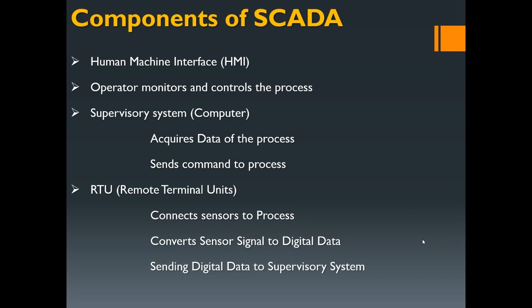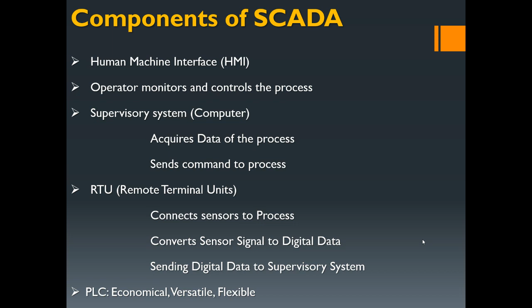Then we have PLCs, programmable logic controllers. They are connected to the sensors and actuators in the process, and they are networked to the supervisory system in factory automation. The PLCs typically have a high-speed connection to the SCADA system in supervisory control. In remote applications like a large water treatment plant, the PLCs may be directly connected to the SCADA over a wireless link, or utilize the RTU for communication management. PLCs are often used for remote sites where there is a large input output count rather than utilizing the RTUs alone.